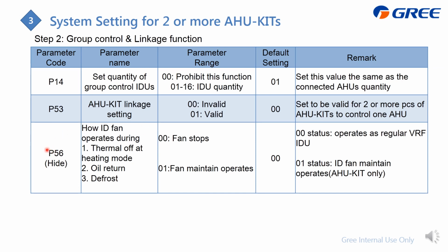And P56 is only for the AHU kit. This is to select how the indoor fan operates during thermal off in heating mode, at oil return, and also at defrost. 00 means the fan will stop, and 01 means the fan will be maintained at the set fan speed.